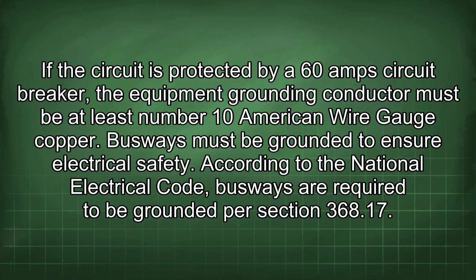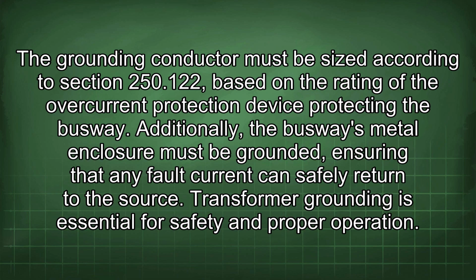Busways must be grounded to ensure electrical safety. According to the National Electrical Code, busways are required to be grounded per section 368.17. The grounding conductor must be sized according to section 250.122, based on the rating of the overcurrent protection device protecting the busway. Additionally, the busway's metal enclosure must be grounded, ensuring that any fault current can safely return to the source.